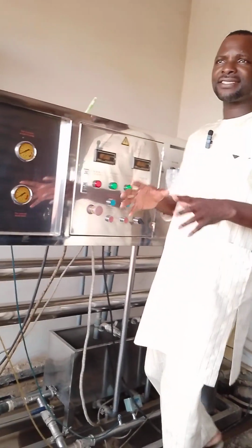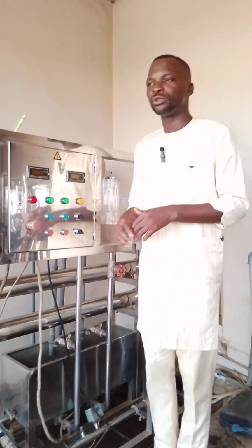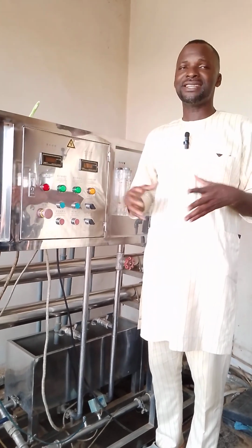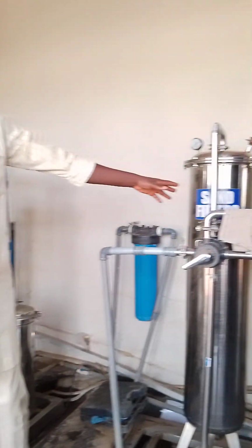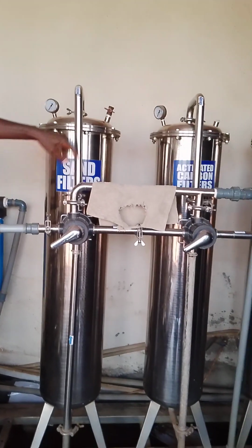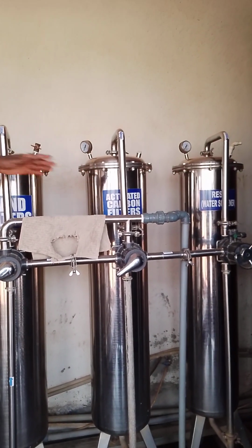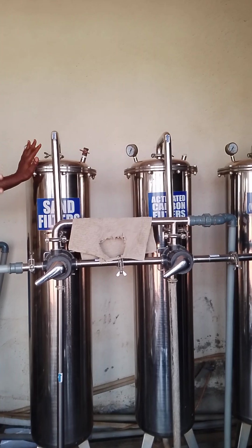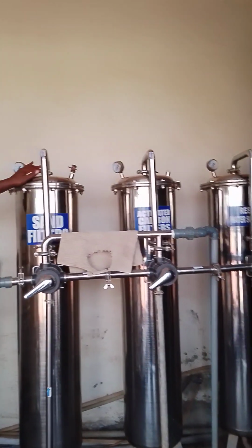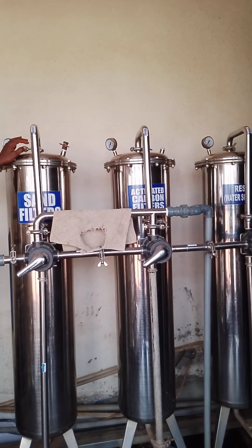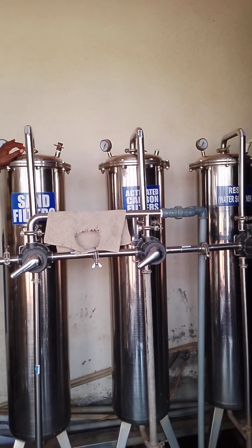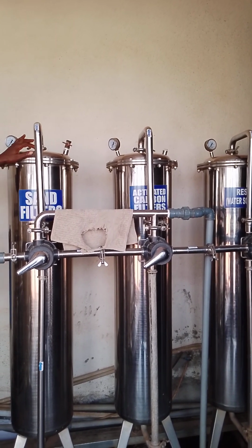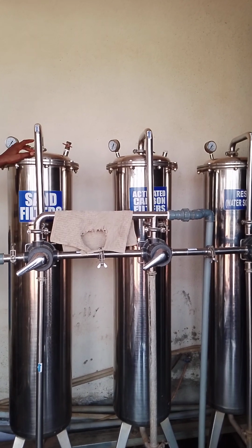And the only advice I need to give you is to ensure that your filtration media, your sand filter, your activated carbon, your resins, have been flushed. If you cannot do it every day because you don't have much volume of water in your factory, ensure that you flush it 3 times a week or 4 times a week. That is, you back flush them properly.